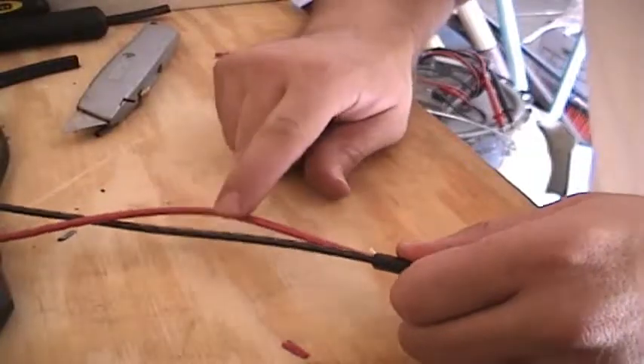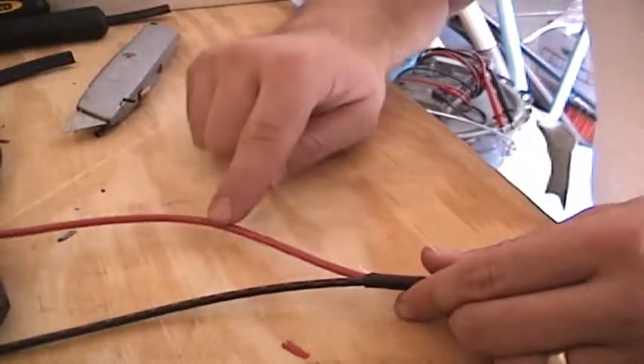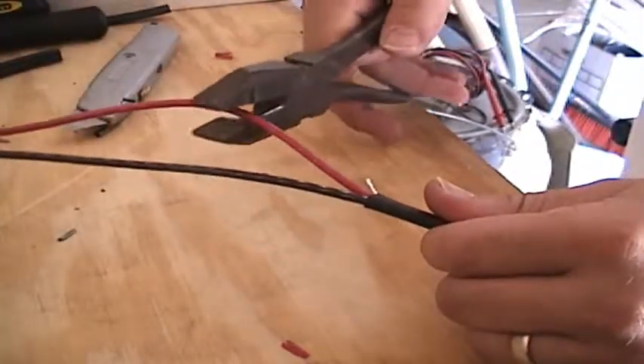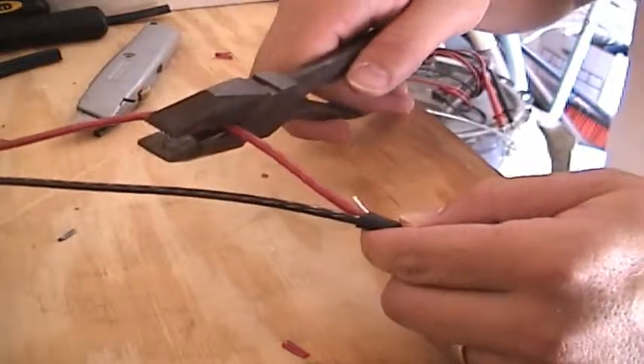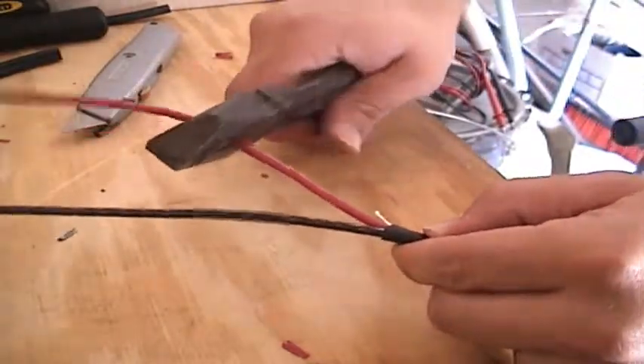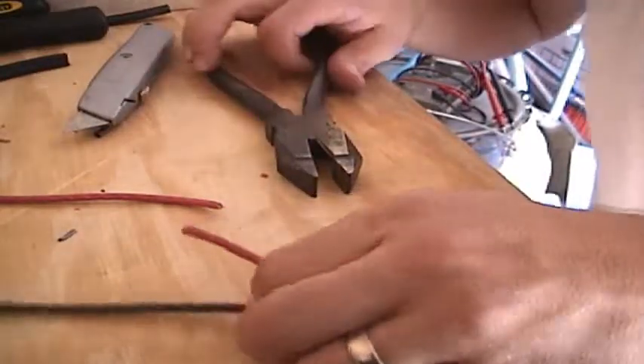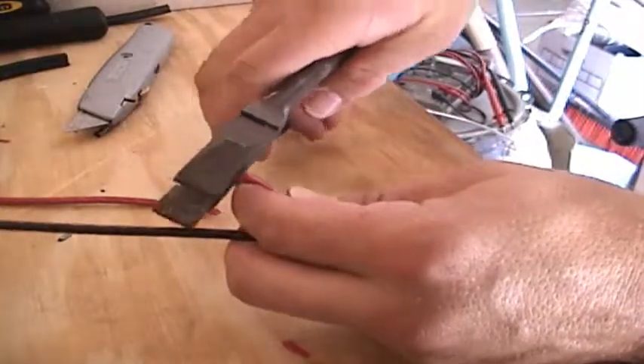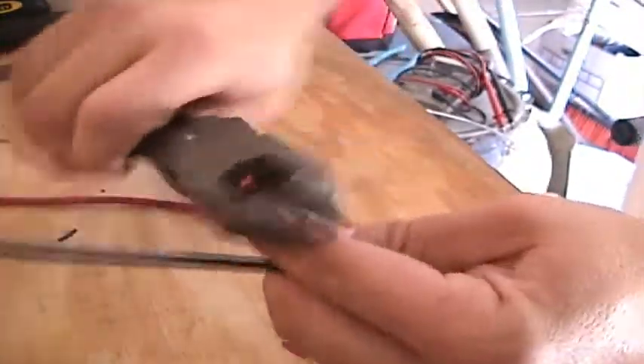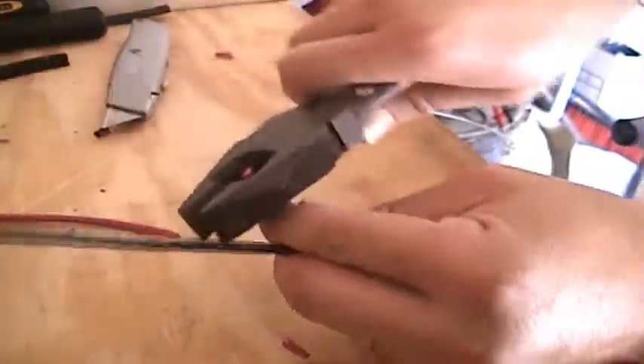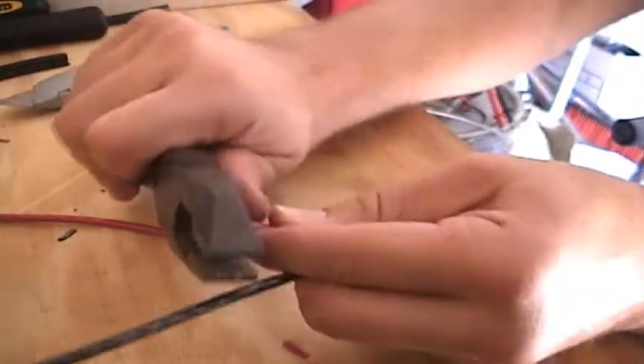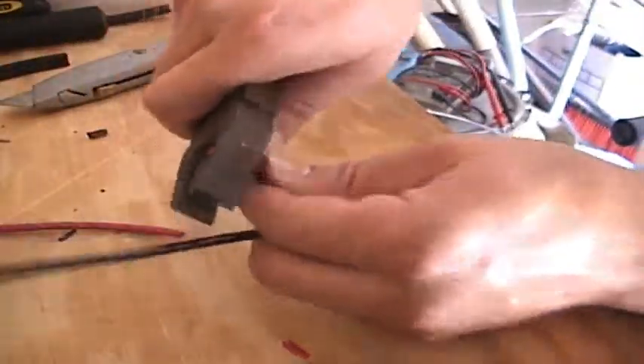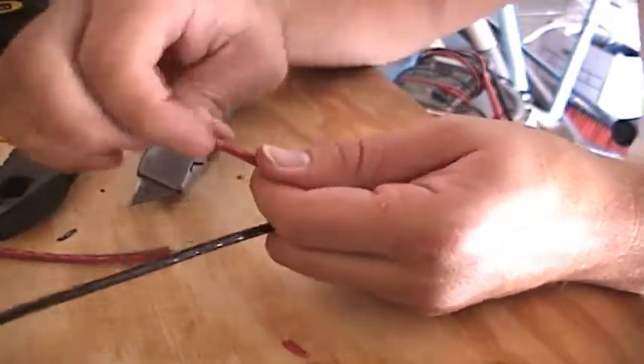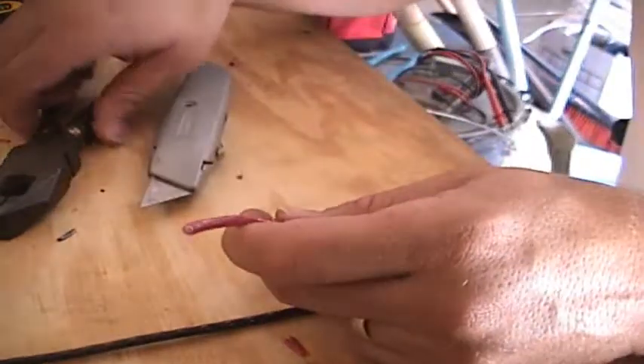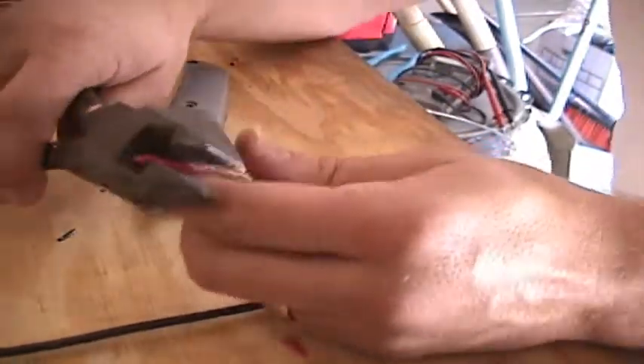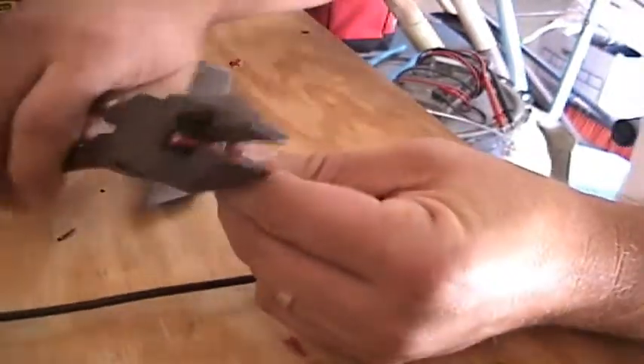Okay, now let's go ahead and cut the red 10 gauge piece of wire with about a 2-inch tail remaining. And then we're going to remove again about 1/2 inch of insulation off the end of that 2-inch tail of red wire. Okay, now let's grab the 12-inch piece of wire. And again, remove about 1/2 inch of insulation off the other end.